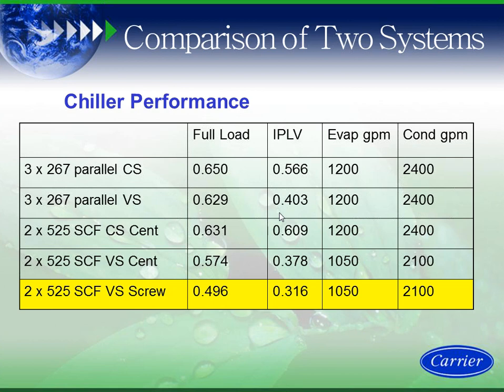Now you're looking at full loads of 0.496, part loads of 0.316. Now you may be asking why my condenser water flow and my evaporator flow are the same. Now I'm doing a variable primary system. I'm doing a variable primary system on the variable speed screw options. On the constant speed 267 ton machines, I'm doing 1200 GPM because I have a primary secondary system. I'm always pumping that GPM.